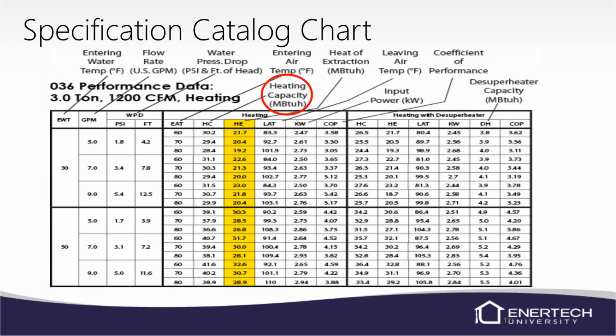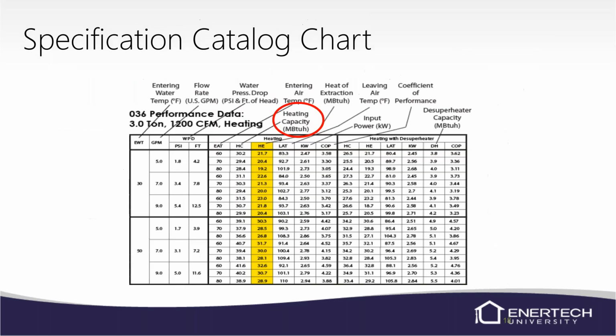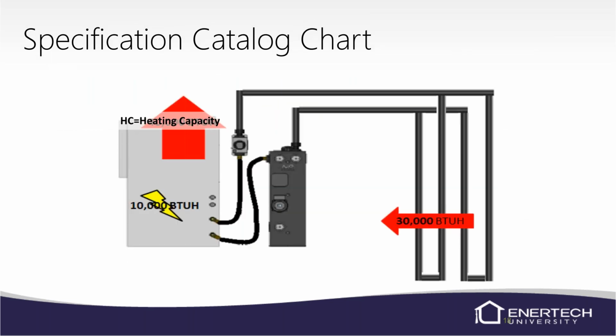The heating capacity, you will see, is a higher number than what is next to it, the HE, the heat of extraction. Heating capacity is basically, you have what's called heat of compression in a system. So you have the heat of the electrical components in the system that we have to do something with as well. In this example, let's say we're pulling 30,000 BTUs out of the loop field. We're also just going to say 10,000 BTUs of heat of compression in the refrigerant circuit that we've got to do something with as well.